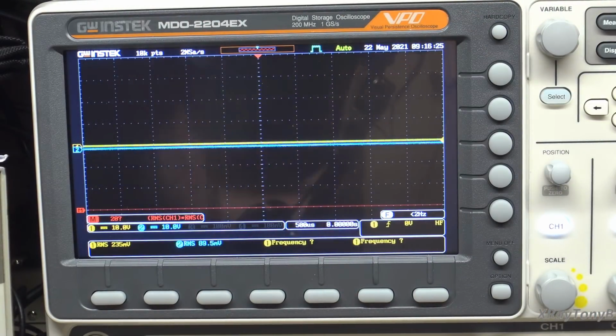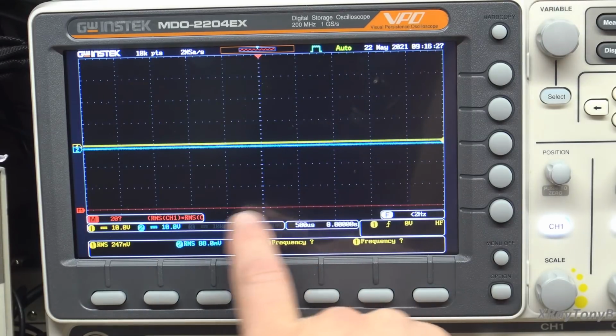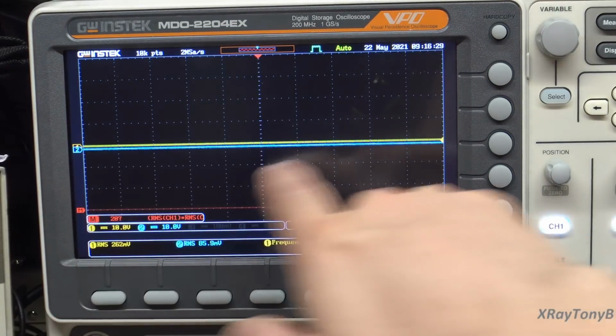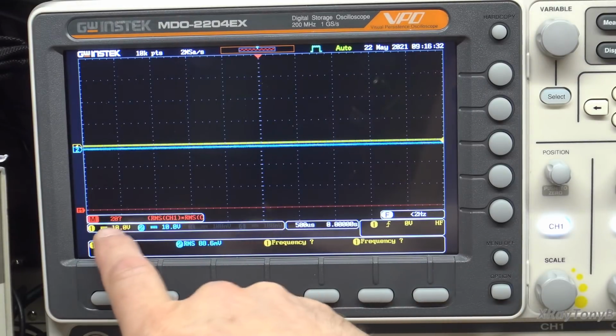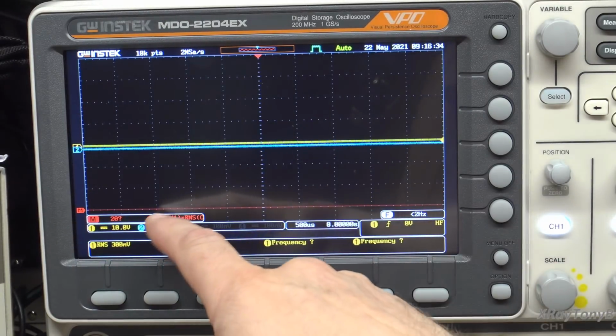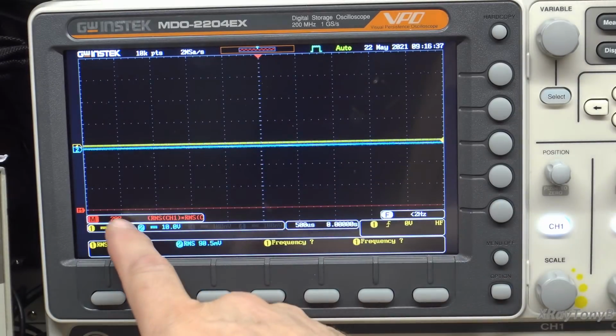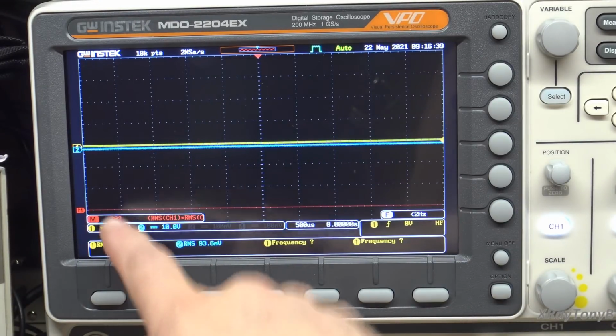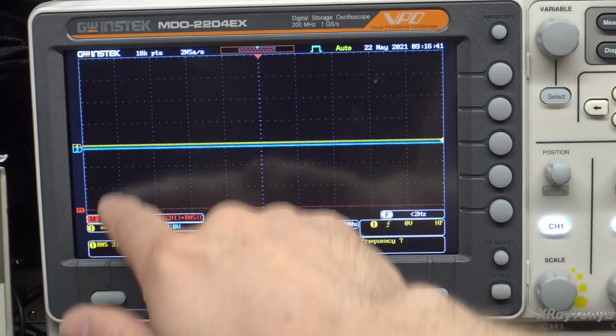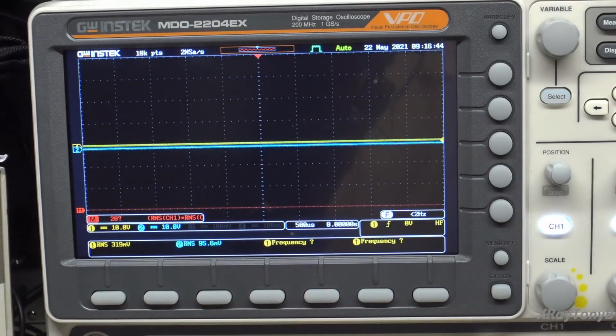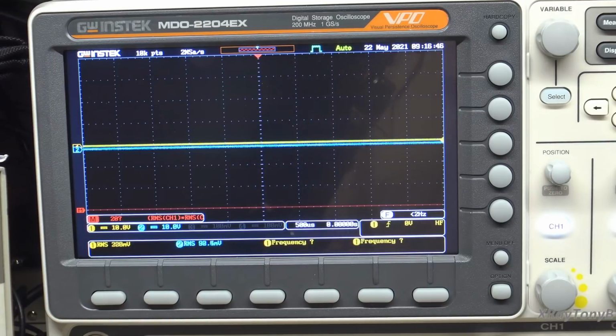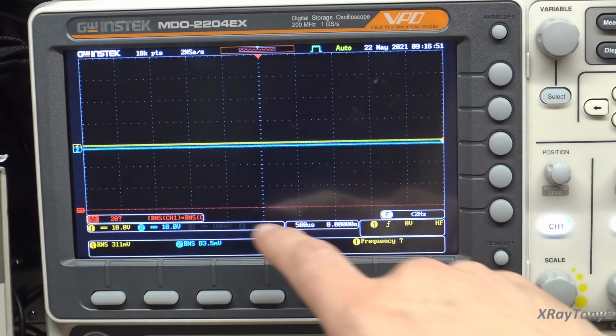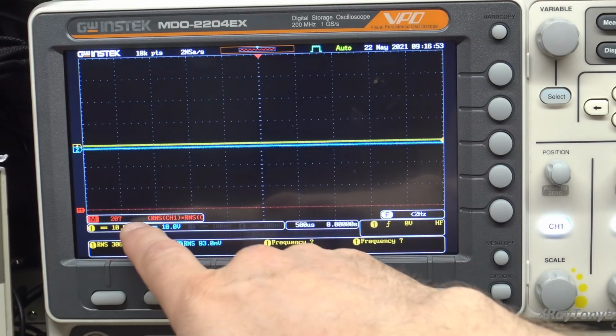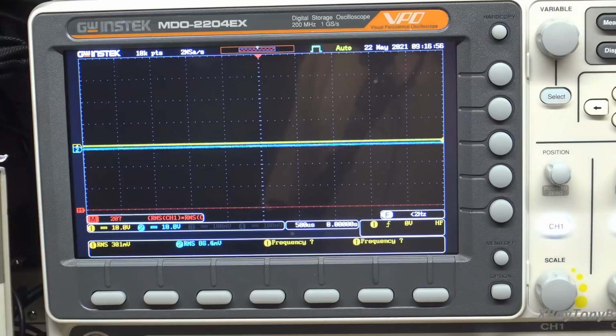So it's a trade-off. The other thing I noticed about the math on this is it shows you the line, but it will not read out the number that it's sitting at. So if you notice it was sitting at 50 watts, it doesn't tell you that it's 50. You actually have to measure it on the scale. So that's kind of a bummer, whereas if you remember the Tektronix, not only did it show you the visual representation of the wattage, but it also put the actual number that it was sitting at in there. This one does not. That's not the end of the world.